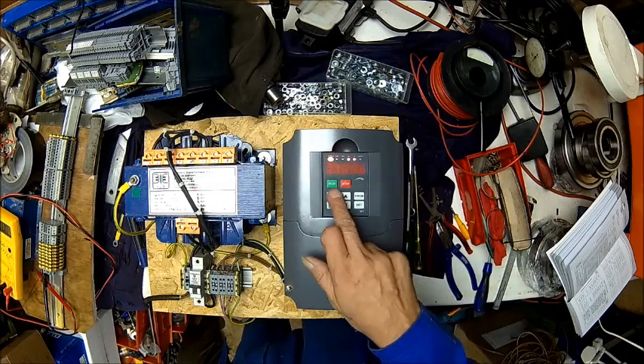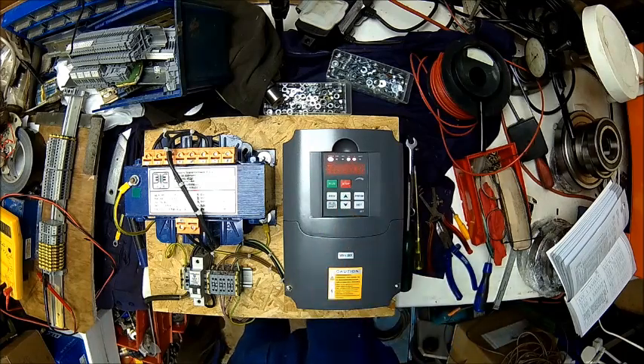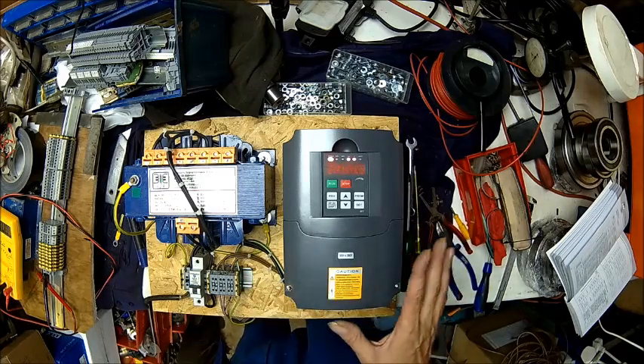630 is fine, and again it drops down as soon as you run, because we have technically a little bit too few capacitors inside. That's the reason why for a 3 kilowatt setup on a 13 amp supply, that's about 3 kilowatts. That's what I get out of it. The 4 kilowatt inverter is just fine.